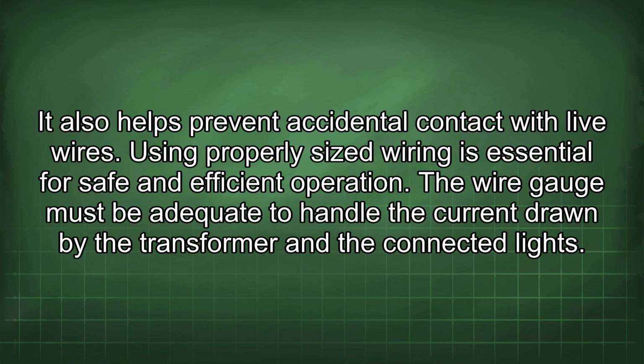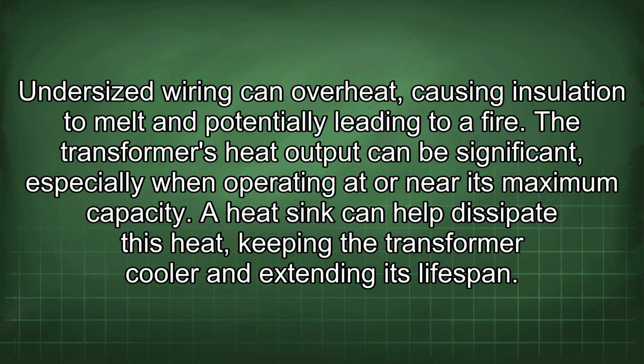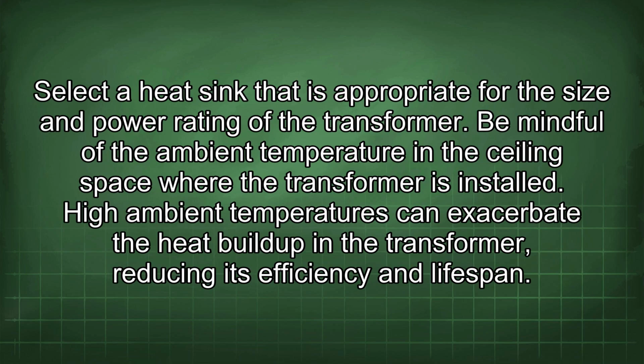Using properly sized wiring is essential for safe and efficient operation. The wire gauge must be adequate to handle the current drawn by the transformer and the connected lights. Undersized wiring can overheat, causing insulation to melt and potentially leading to a fire. The transformer's heat output can be significant, especially when operating at or near its maximum capacity. A heatsink can help dissipate this heat, keeping the transformer cooler and extending its lifespan. Select a heatsink that is appropriate for the size and power rating of the transformer.